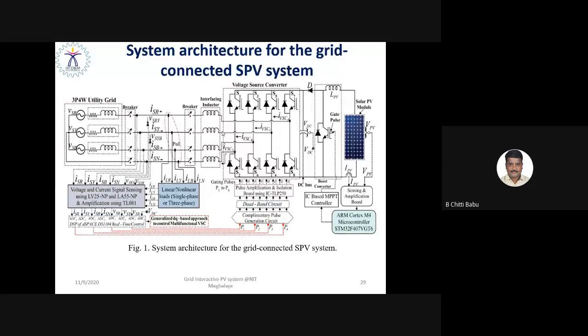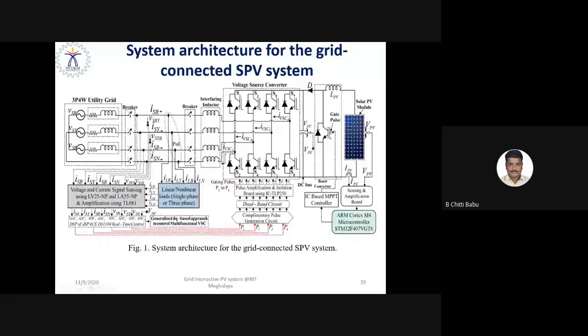Then the inverted AC, or controllable AC, is fed into the utility grid in the form of active as well as reactive power through a breaker and interfacing inductor. So as we provide the control algorithm to the voltage source inverter for internal current control and outer voltage control loop, basically it has a control circuitry. That control circuitry includes voltage and current sensing elements, as well as the amplification unit and the blanking circuit, as well as the power supply unit, including isolation. So we are able to generate the PWM pulses to the three-phase four-legged inverter so that you are able to achieve the desired control. You are able to apply your implemented control algorithm so that you can achieve your objectives.